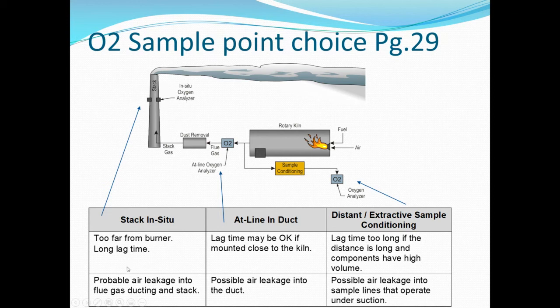But in situ in the stack, what's the problem with this here? Well, it's too far from the burner and there's a really long lag time.